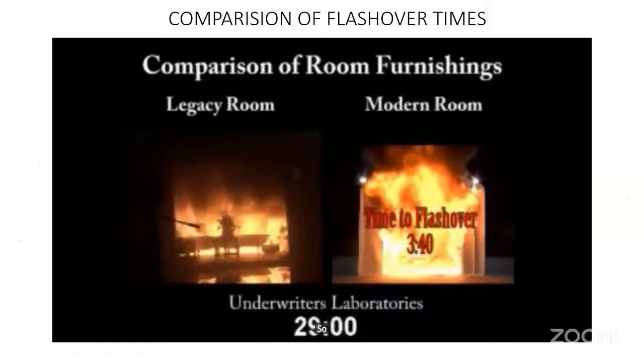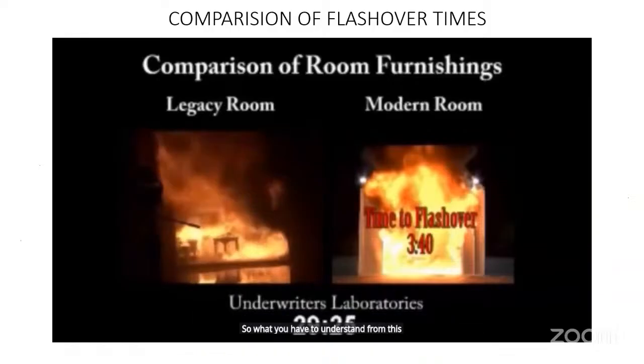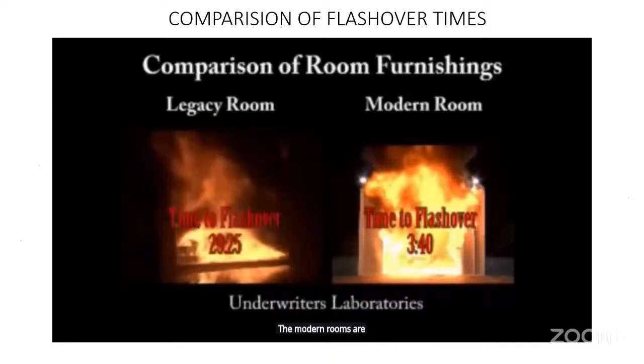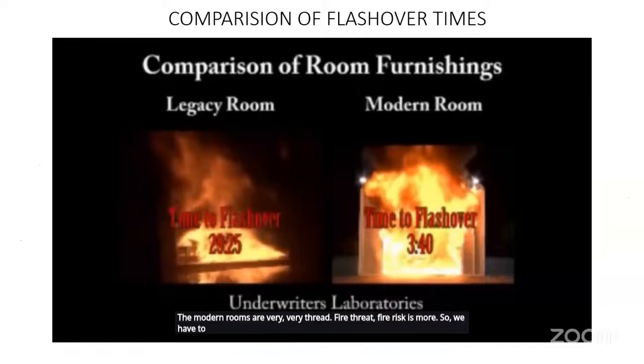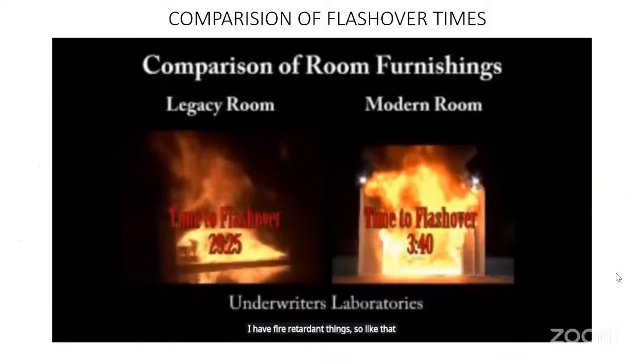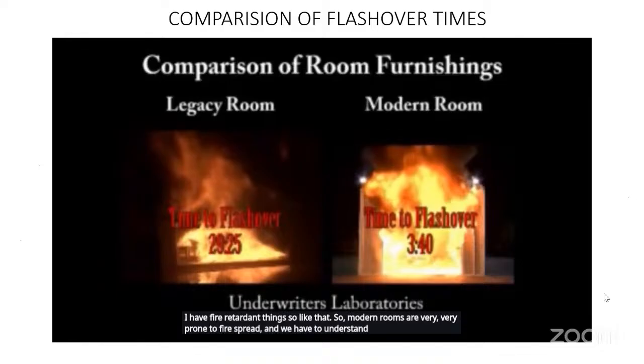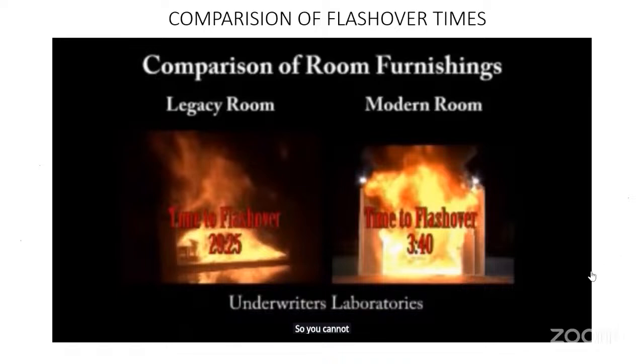So what you have to understand from this, the modern rooms' fire risk is more. So we have to make our fire prevention systems, fire protection systems, and the selection of flammable materials, combustible materials, such that we can have fire retardant things. So modern rooms are very, very prone to fire spread, and it's not like a legacy room. If any fire happens in any building, it is a matter of 5 minutes to complete the fire spread. So you cannot wait for any public fire services.